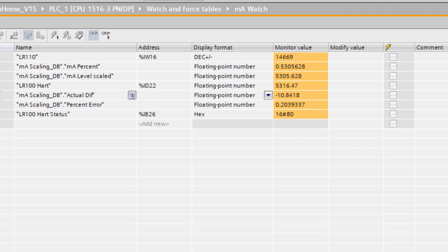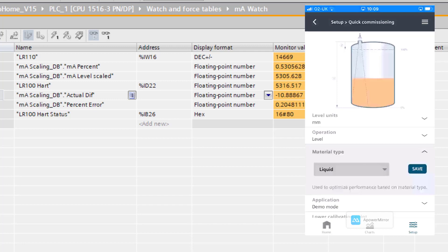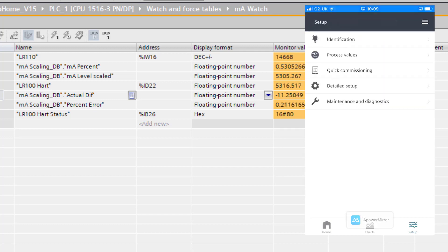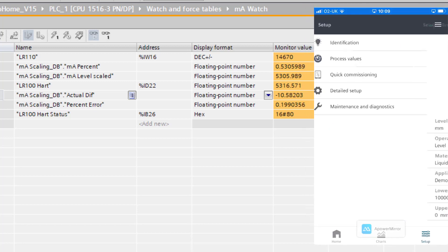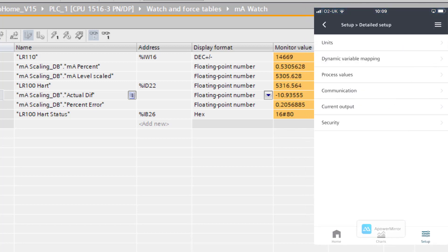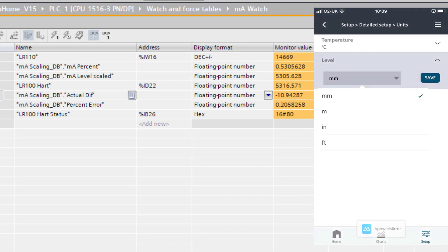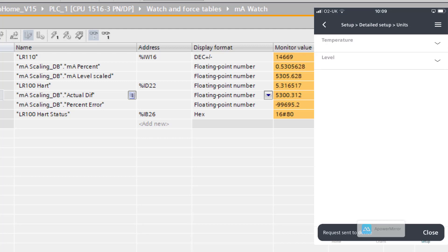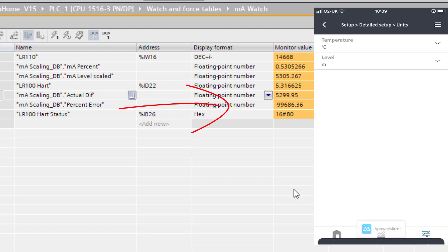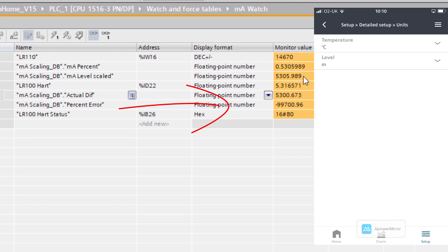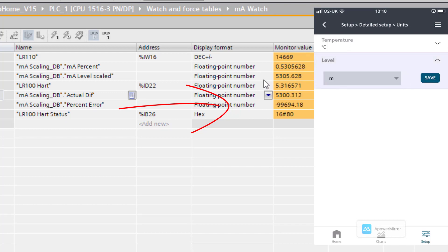At the moment everything is scaled correctly. I'm connecting with the Bluetooth app and I'm going to go into my setup and just change the units. This is not a big issue as far as the device is concerned because it changes everything to where it should be. We can see over HART I'm now in meters, and there's my milliamp value — I'd have to change my PLC code to get that to represent the same thing.